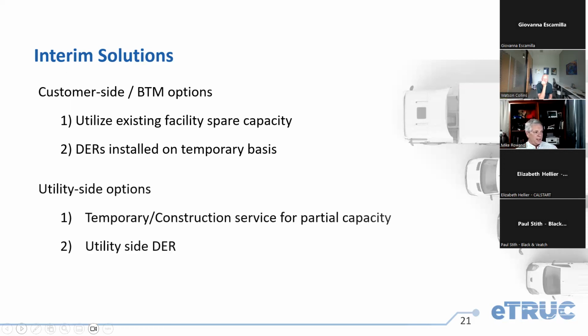Then on the utility side, you have similar options. You can use utility side DER, which has some advantages. But one of the things we talk about in the report is the utilization of a temporary construction service for partial capacity. If you think about it, the common paradigm on building structures in the utility, if somebody's building a 2 megawatt building, everyone expects and assumes that temporary power is going to be needed. I need a few hundred kW for construction until my permanent service gets delivered. So how can we use that paradigm in large EV charging projects?